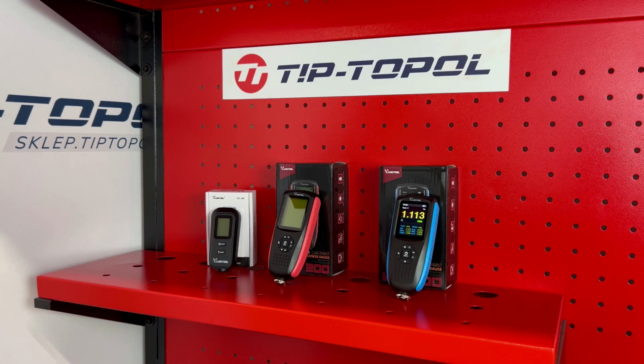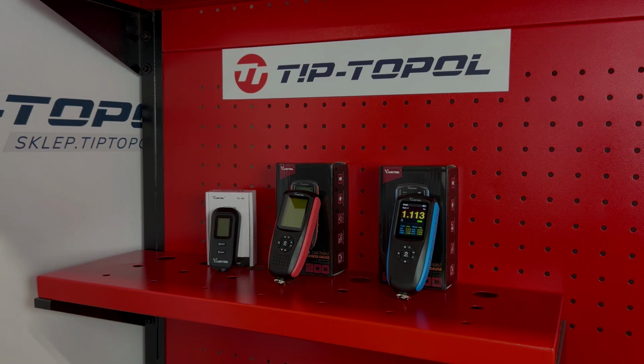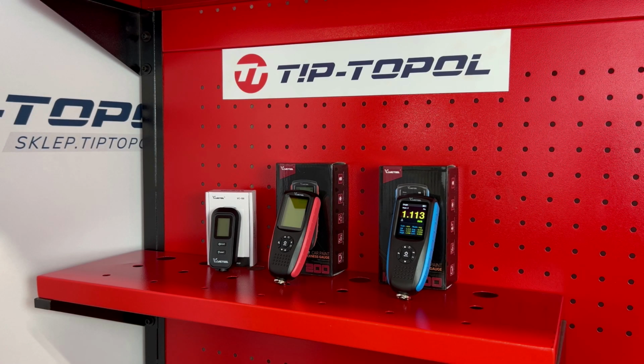A significant difference in these gauges is that the first gauge operates on replaceable button batteries. The other 2 gauges have rechargeable batteries that are charged via a USB cable. An important piece of information about all 3 gauges is that they can measure both steel and aluminum surfaces.